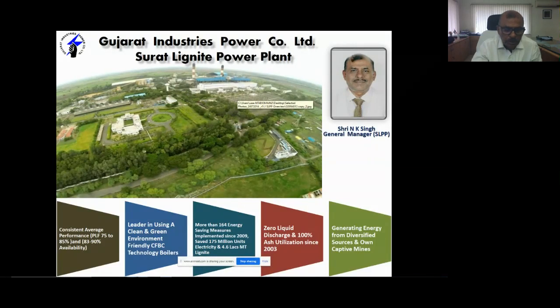The plant is based on CFBC technology, having 4 units, each of 125 megawatt, and total capacity is 500 megawatt. We have highlighted something related to performance, mainly on efficiency and energy parameters here. The plant has achieved a plant load factor in the range of 75 to 85% based on the grid demand and other factors. The availability is in the range of 83 to 90%, and that is considered to be one of the best availabilities for a CFBC technology power plant. I will just tell about this in the next slides.